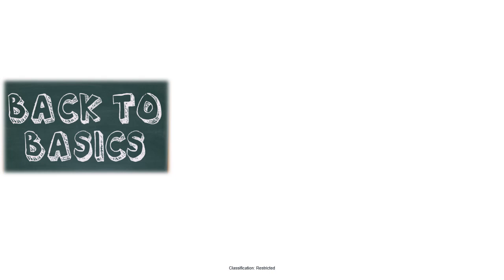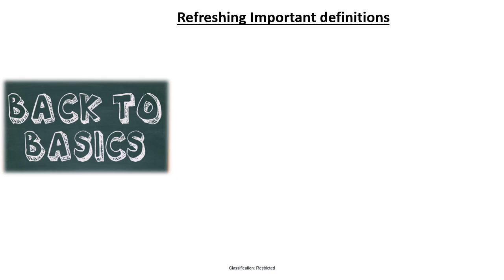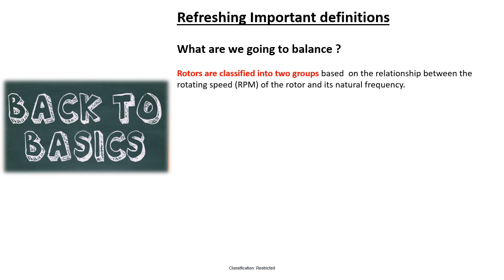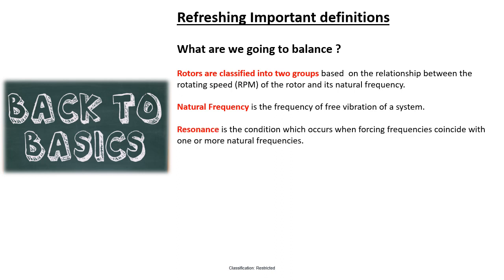Before going to the topic, let's refresh some important definitions. We are going to balance rotors, which are classified into two groups based on rotating speed and natural frequency. Natural frequency is the frequency of free vibration of a system — all machines and machine components have a number of natural frequencies. Resonance is the condition which occurs when the forcing frequencies coincide with one or more natural frequencies, which amplifies vibration.